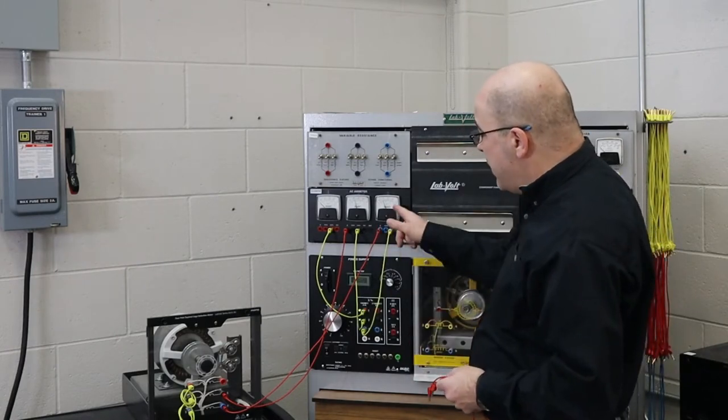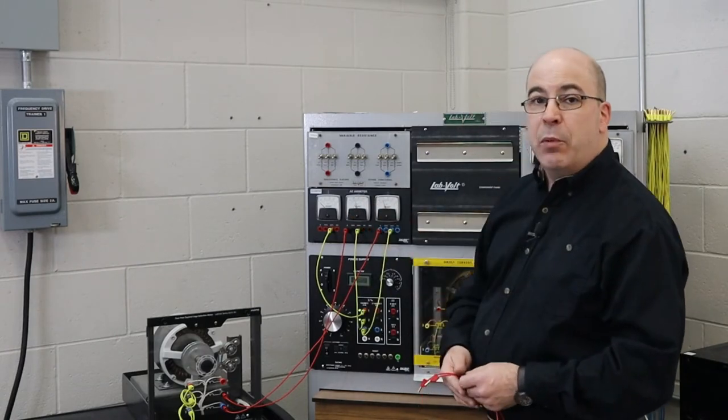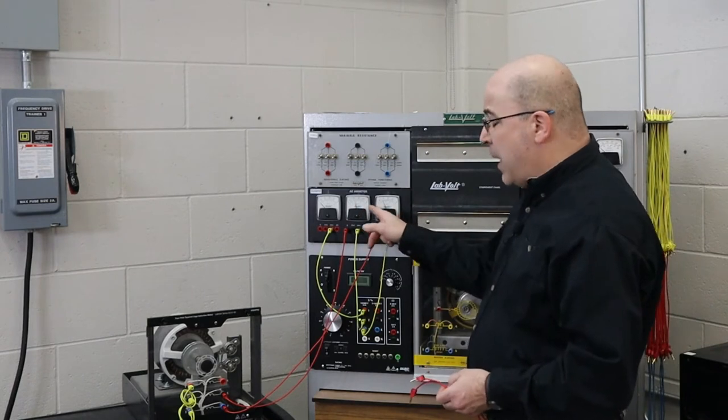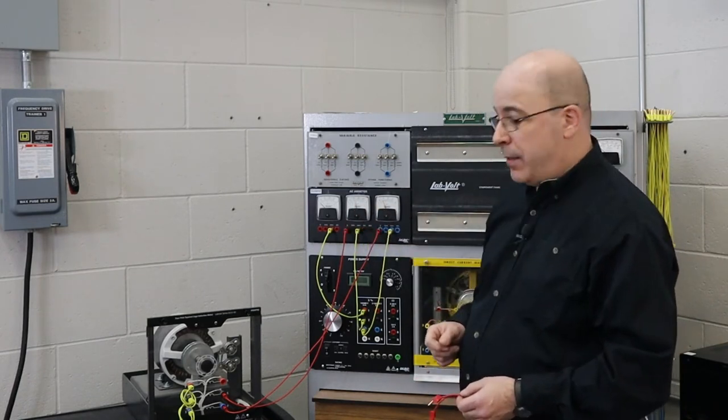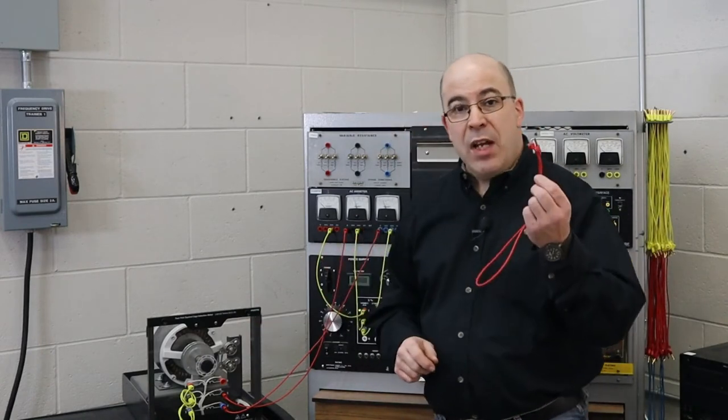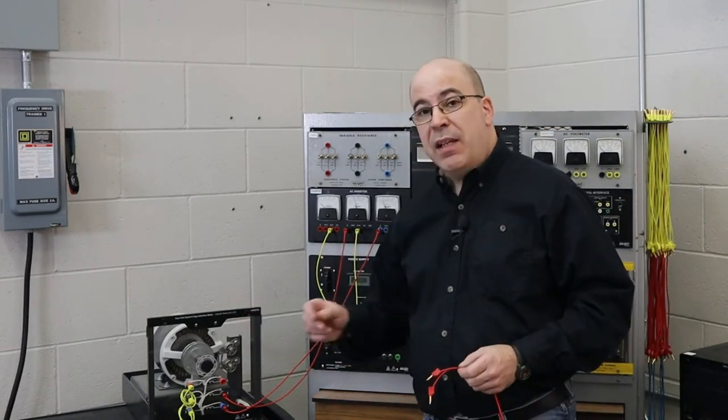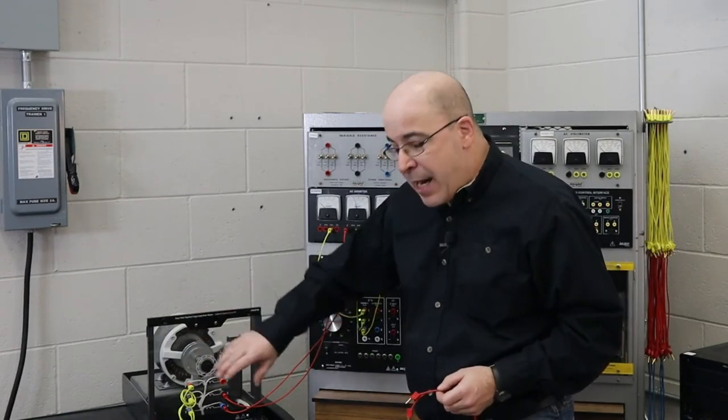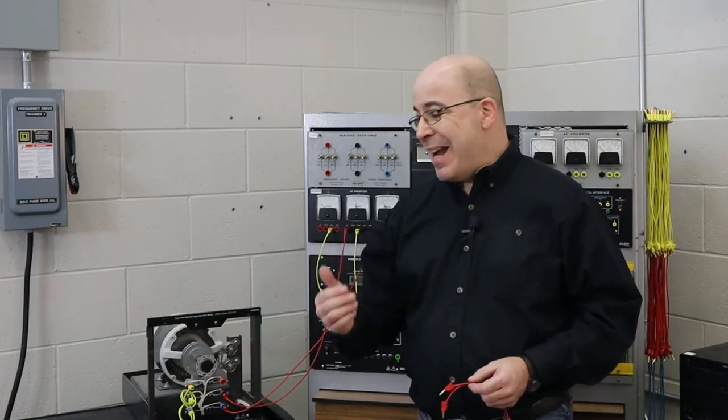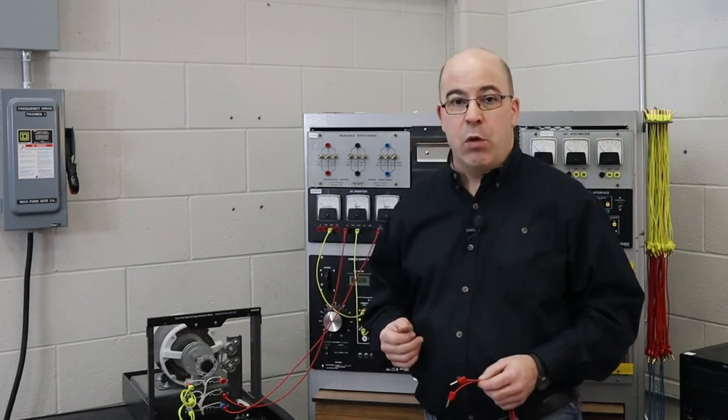What's happening though is that the other two phases that were in operation are now having to kind of split the load and you're seeing an increase in current. As well because I've lost a phase I've also lost a little bit of the horsepower rating. If this was rated at a quarter of a horsepower now we're a little bit less than a quarter horsepower.